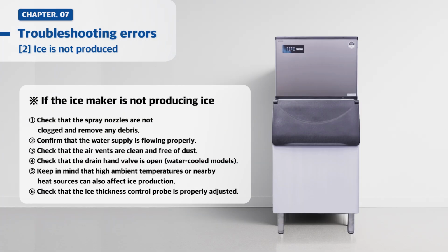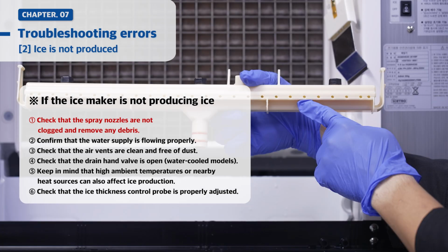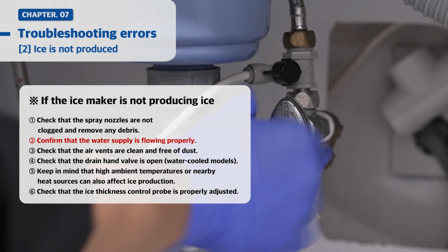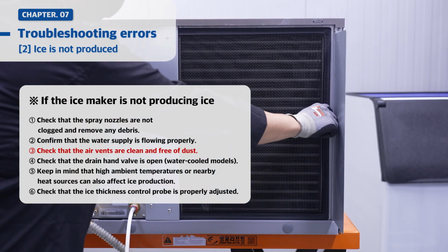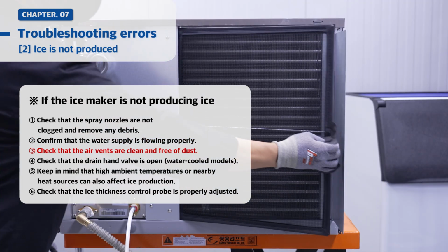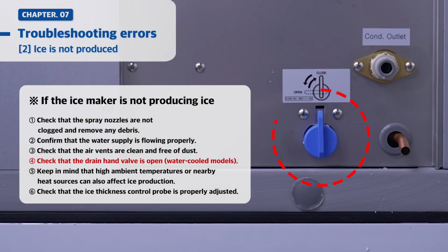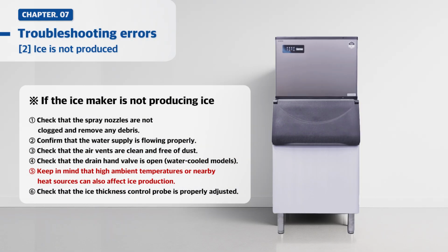If the ice maker is not producing ice, check that the spray nozzles are not clogged and remove any debris. Confirm that the water supply is flowing properly. Check that the air vents are clean and free of dust. Check that the drain hand valve is open. Keep in mind that high ambient temperatures or nearby heat sources can also affect ice production.